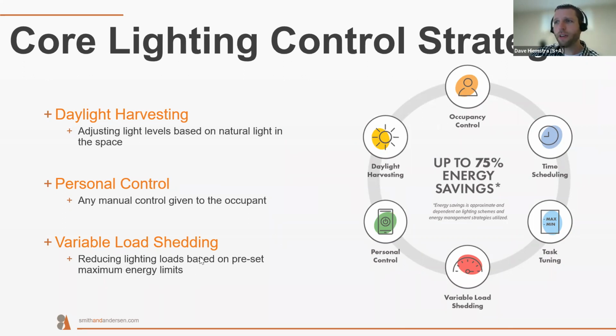Lastly, variable load shedding is the ability to have a maximum threshold of energy usage in the building, and we start cutting loads as much as we can if we're nearing that threshold. Very important in the net zero world of things, where you need to manage your energy usage and not go over certain thresholds that are important for that building. Still not seeing a lot of that in Alberta, except for those really special projects we've done quite a bit of work on.